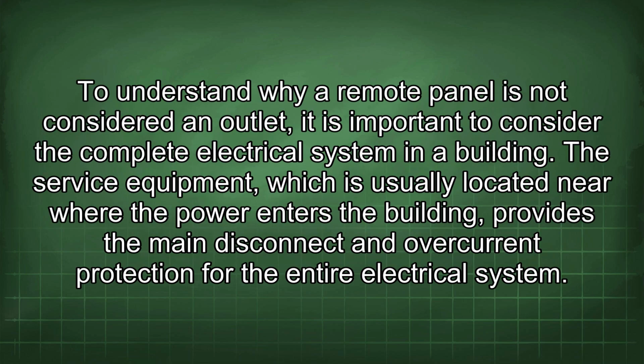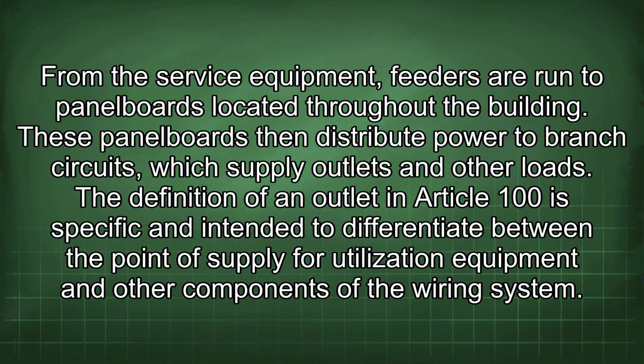To understand why a remote panel is not considered an outlet, it is important to consider the complete electrical system in a building. The service equipment, which is usually located near where the power enters the building, provides the main disconnect and overcurrent protection for the entire electrical system. From the service equipment, feeders are run to panel boards located throughout the building. These panel boards then distribute power to branch circuits, which supply outlets and other loads.